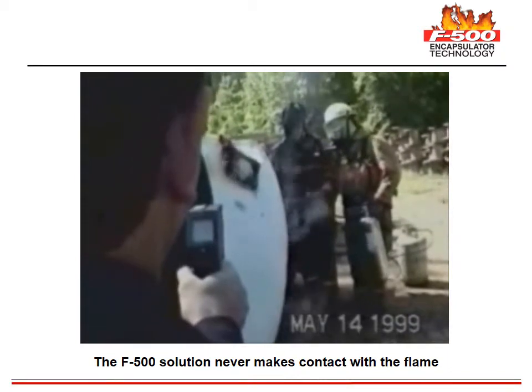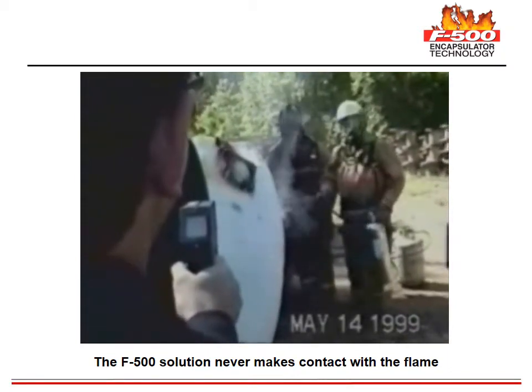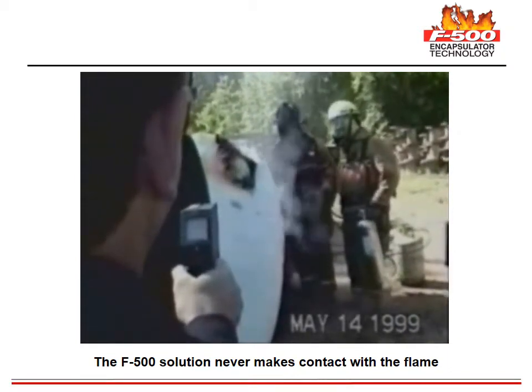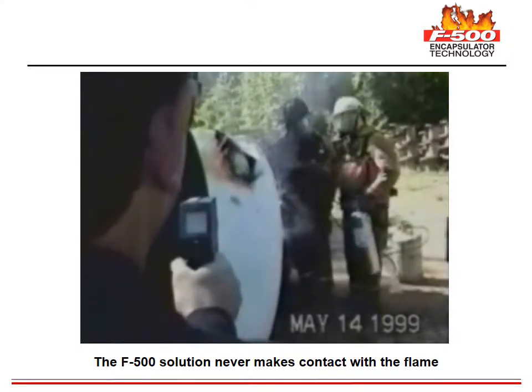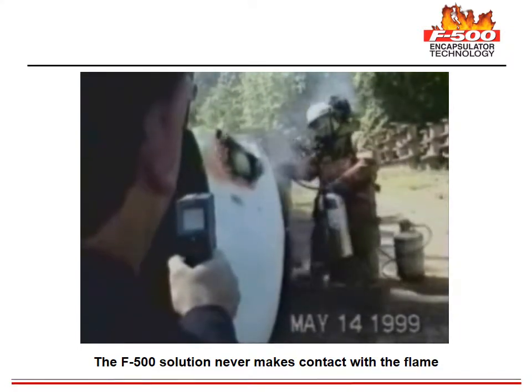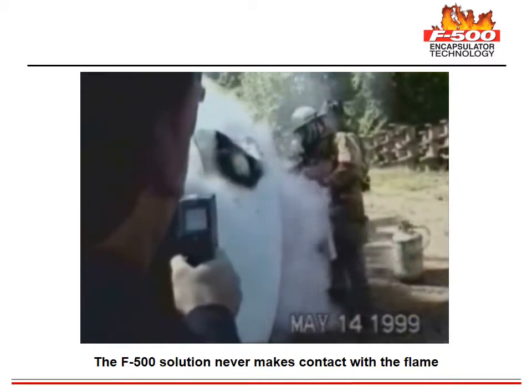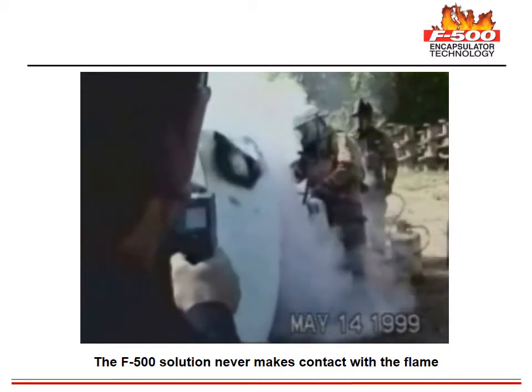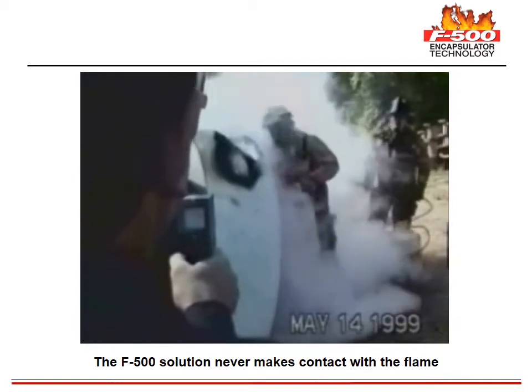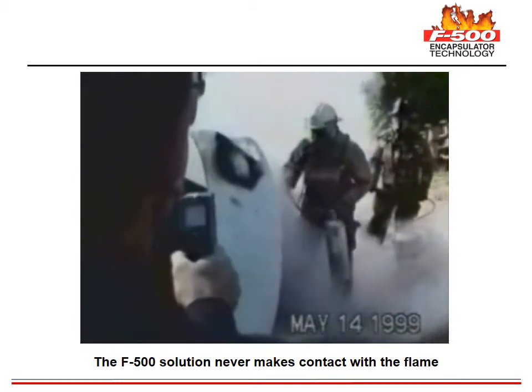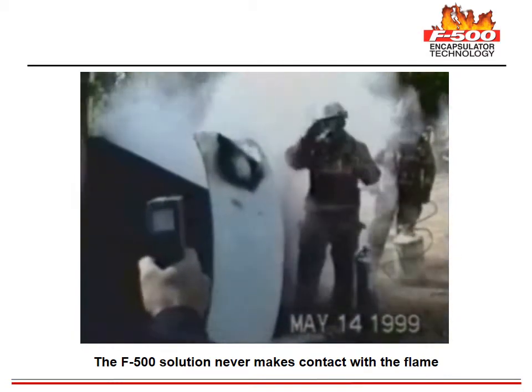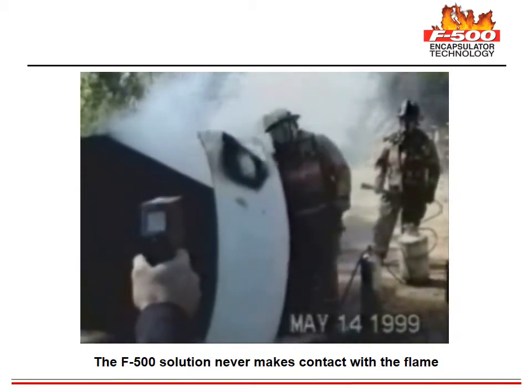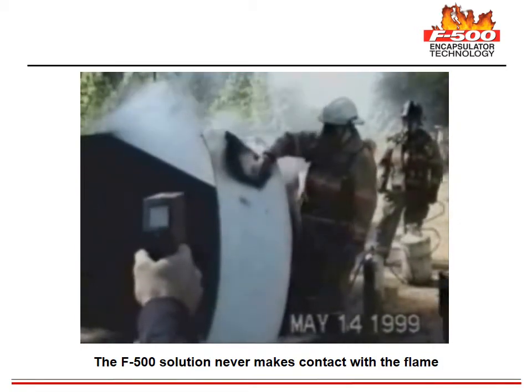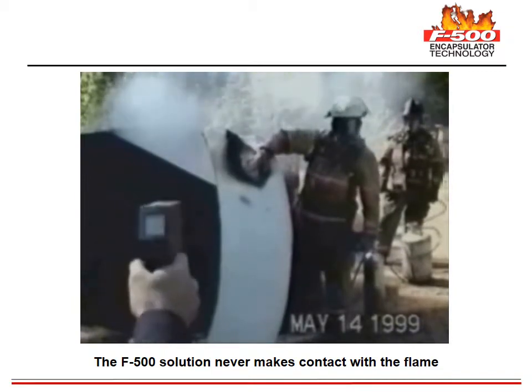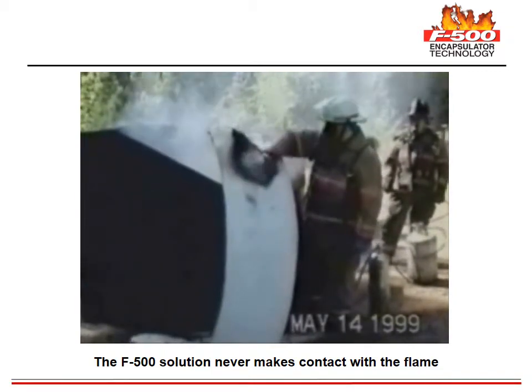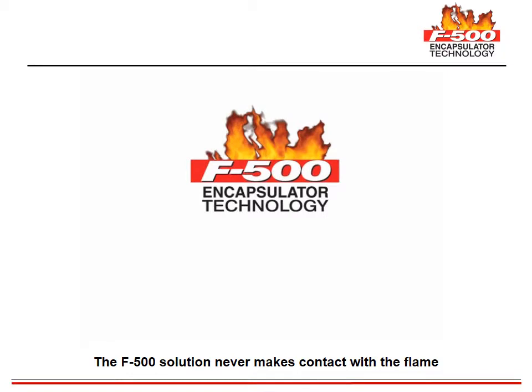A 2.5-gallon fire extinguisher with a pint of F500 encapsulator agent is used to apply the F500 mixture to the steel. In seconds after applying the mixture, the temperature has dropped from 1300 degrees to 100 degrees, and the surface fire is automatically extinguished due to permanent heat reduction. The firefighter is able to remove his glove and place his hand on the steel. Neither plain water nor any other additive can achieve cooling results like this.